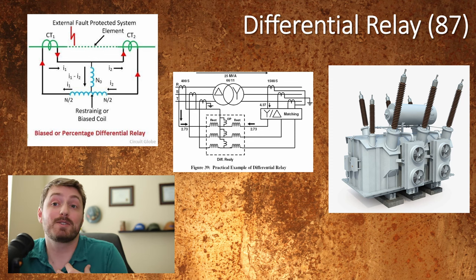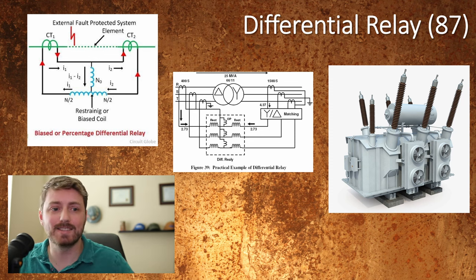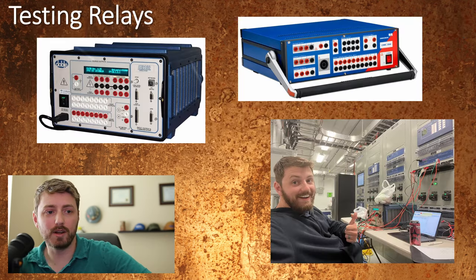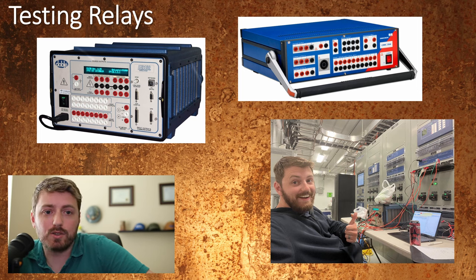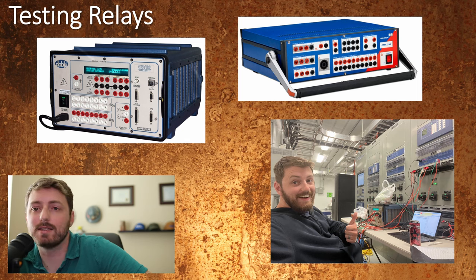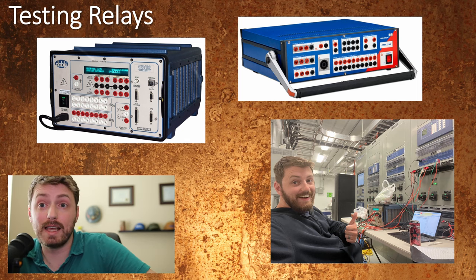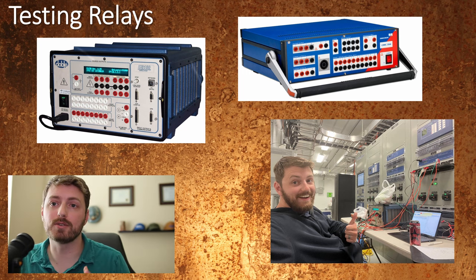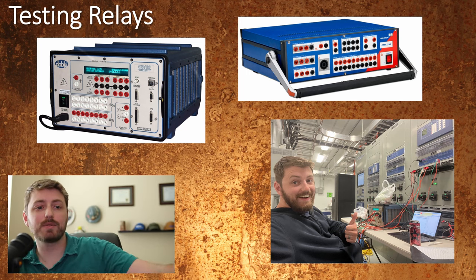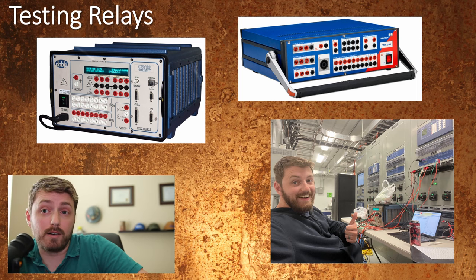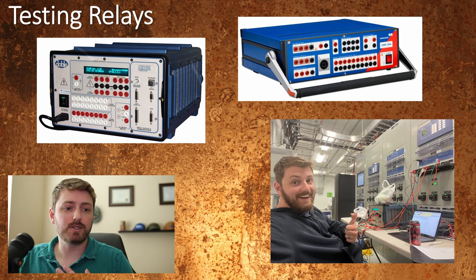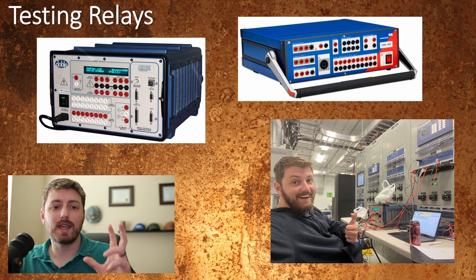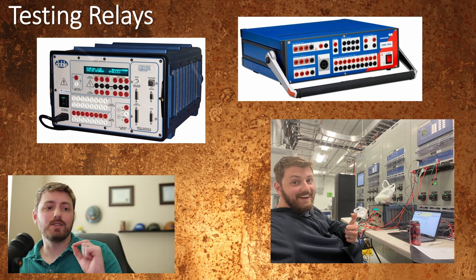But at the end of the day, our job is to make sure they work right — we're relay testing techs. How do we prove they work? For the most part, you're going to be using a purpose-built, software-controlled, high-precision multi-function relay test set to simulate faults. That's what we do — we simulate all of the things that we're trying to protect the power circuit from. Overcurrent, under voltage, differential, synchronizing — all of those can and need to be tested, and I'm going to show it to you.